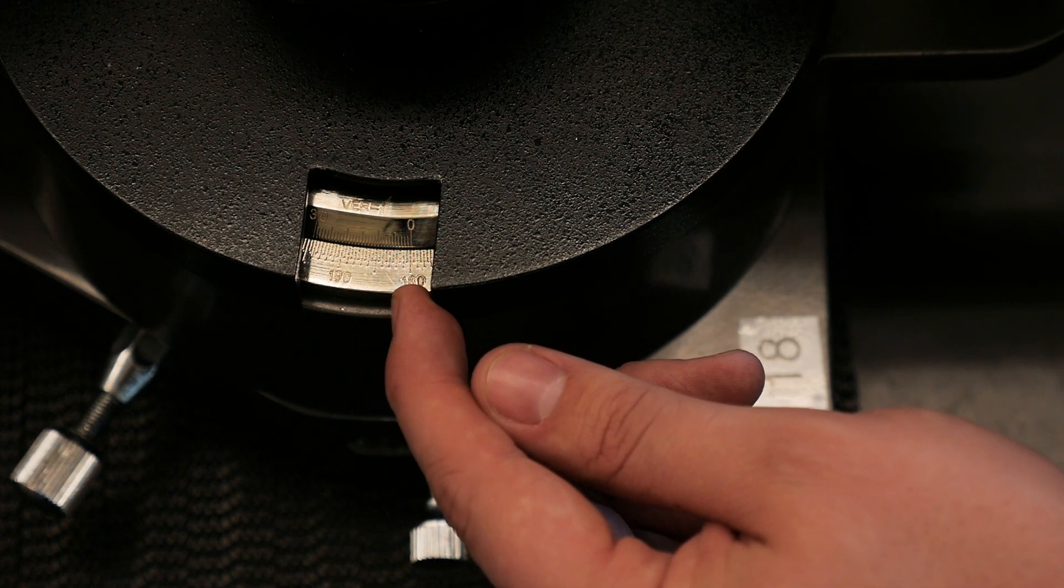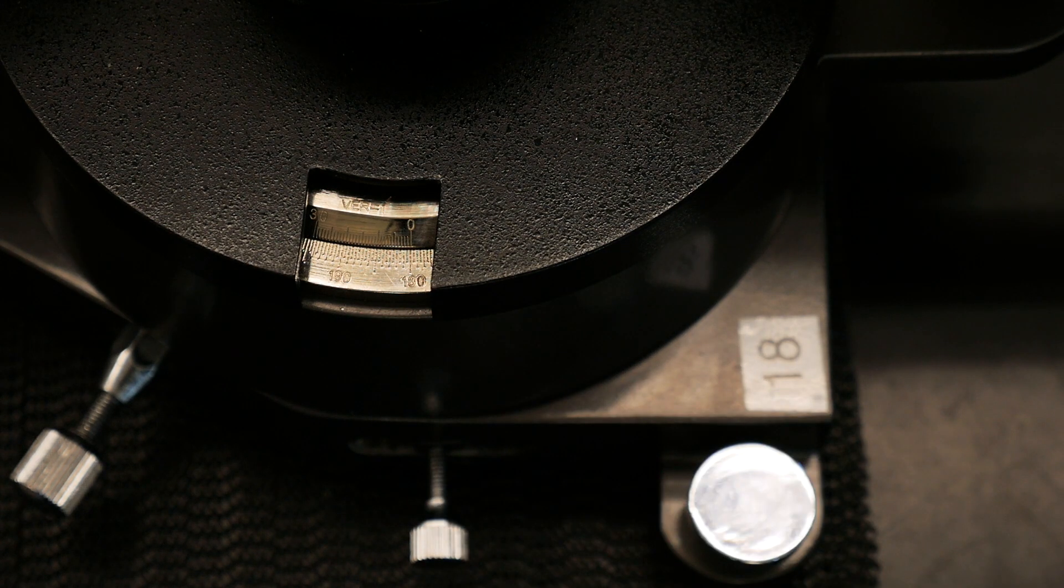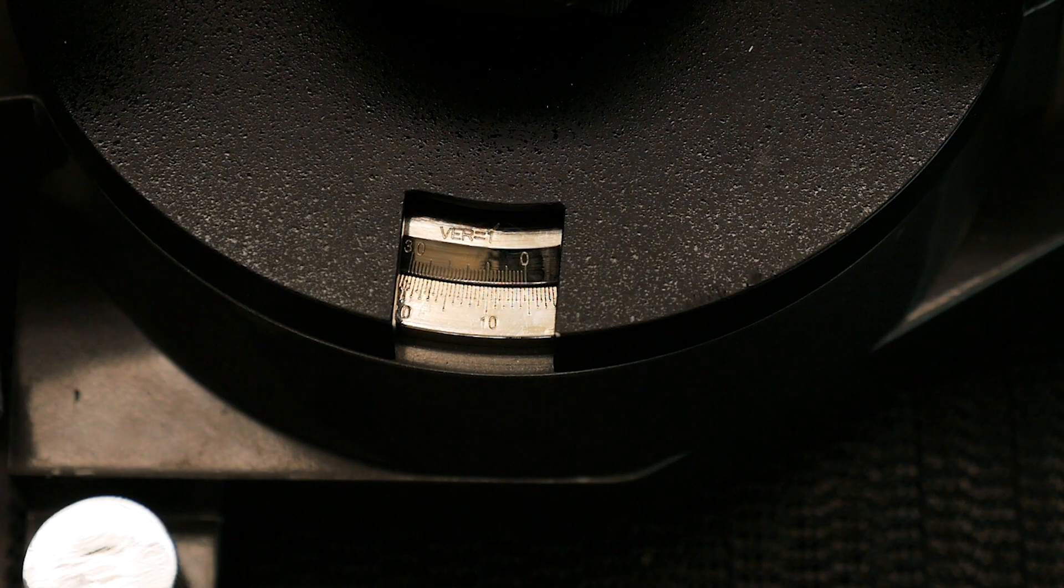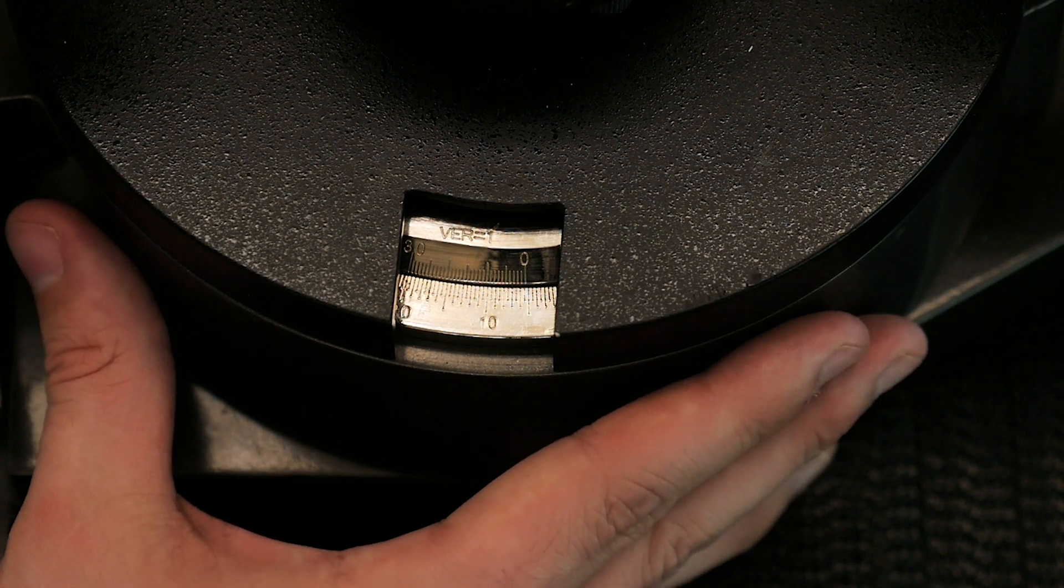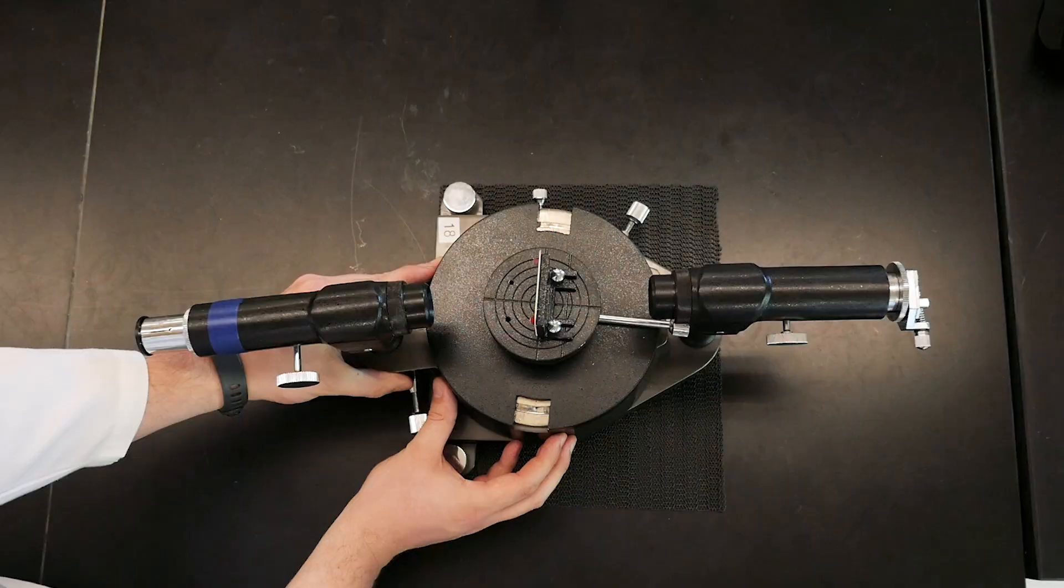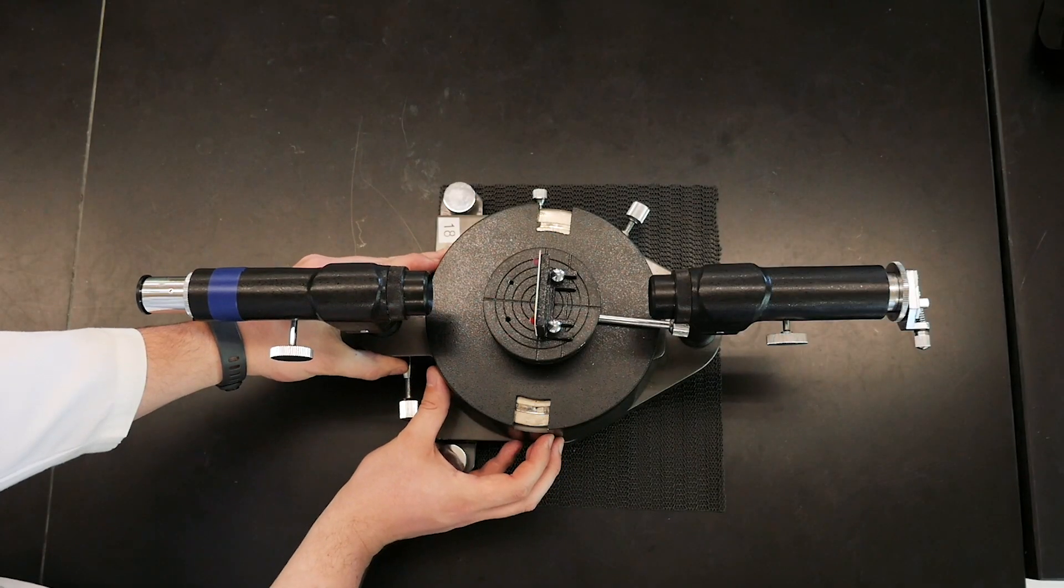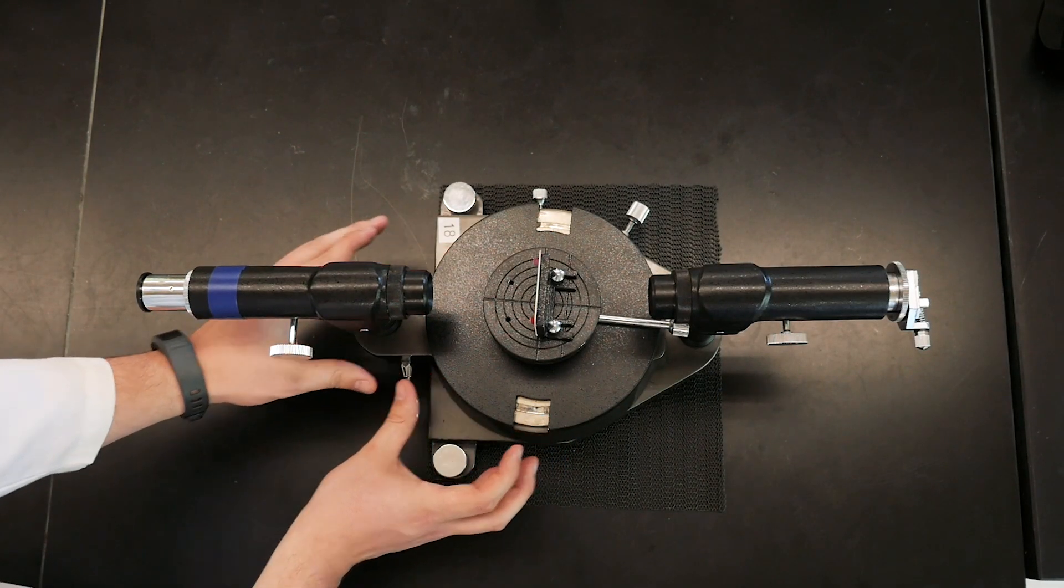The angle can be read by looking for the point where the zero on the top scale crosses the bottom scale. Here you can see that the reading is about 5.2 degrees, so we'll adjust to zero. All right, now that the instrument is aligned, we'll need to make sure it's calibrated properly.